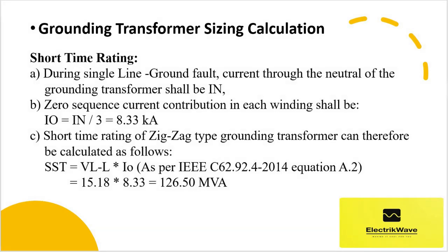Let's calculate the short time rating. (a) During a single line-to-ground fault, current through the neutral of the grounding transformer shall be In. (b) Zero sequence current contribution in each winding shall be I0 = In/3 = 8.33 kilo-amperes. (c) The short time rating of the zigzag type grounding transformer can therefore be calculated as follows.